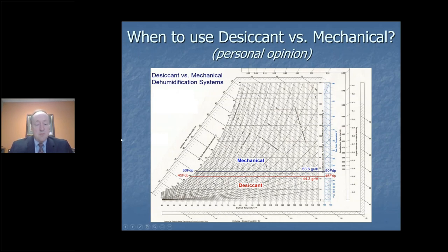And then there's an area in between. I call this the gray zone. I might go either way. It depends on how critical it is. If I ask the client, you told me you wanted 45 degrees, what happens if you go to a 48 degree dew point? Oh, that's not a big deal. We're not worried about that. Okay, then I probably wouldn't spend the additional money, the capital cost as well as the operating cost, of putting in a desiccant-based system if it's not that critical. But if it is, then I would lean toward the desiccant. So that's just my rule of thumb.